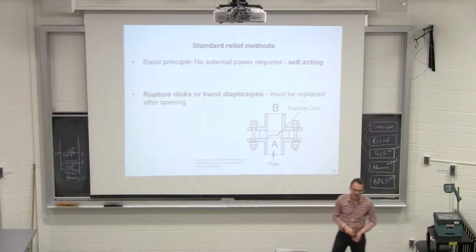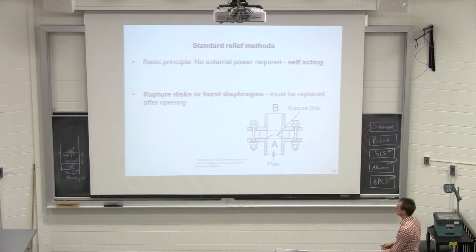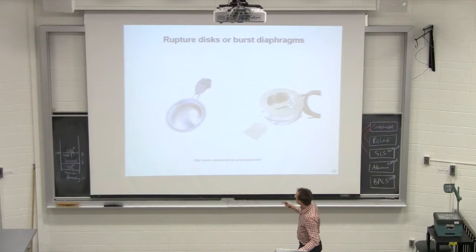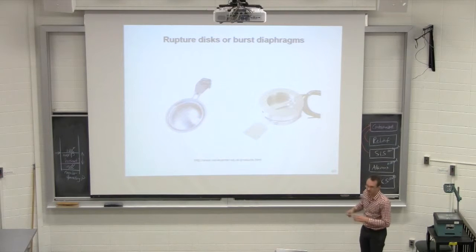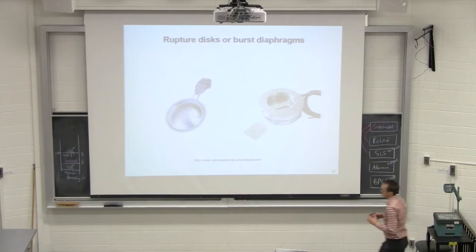Okay, so that's one type of relief. The second type of relief is a lot less costly. These are called rupture discs. And unlike the relief valve I showed you, they don't need electricity to operate. This burst disc is a hemispherical device. There you can see one. So these small lines are grooved into that hemispherical disc end, and they will open up once that pressure is achieved.